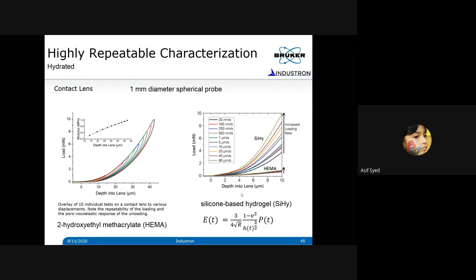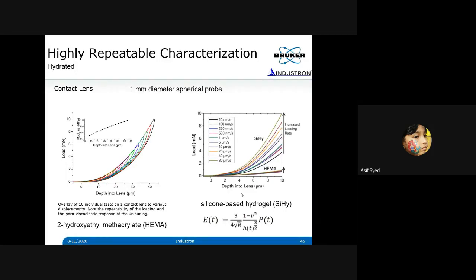The one thing that I want to point out is all these experiments were done in a hydrated condition, which means submerged in a buffer solution. When you do that, you don't have much of an adhesion problem. This is the one trick people use. When you have a probe making contact on soft materials like this in a dry condition, you have the problem of adhesion between the tip and the sample. To avoid that, and most of the time you have to test in a hydrated condition anyway, when you do it in a submerged condition, you can minimize this adhesion. That's why you can see in this load displacement curve there is no attraction, jumping in and jumping out, or any of those characteristics. I'll show that type of curve real soon.